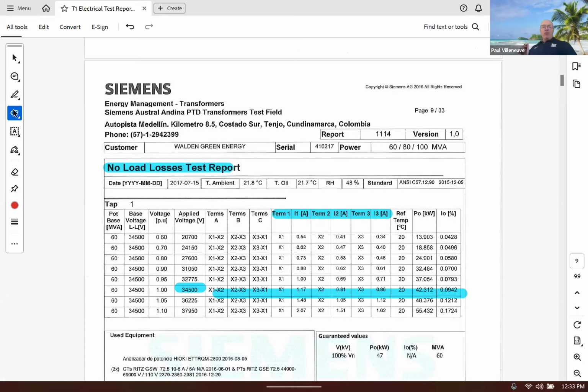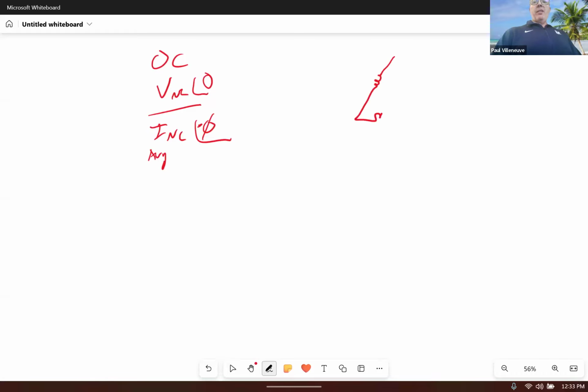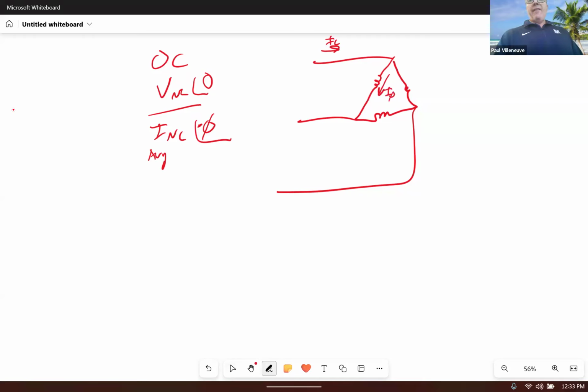That's all I did. But here's where I got to be careful, because on a delta, here's my transformer and my delta windings. I'm measuring this current, which is a line current. The actual impedance I'm trying to get is in that leg. So that's a phase current. So I have to take the no load average and divide that by the square root of 3, right? I've got to convert that to a phase current. Now, the voltage over here is a line voltage, but that's also the exact same voltage across that individual element. So in this case, I don't need to divide the no load voltage by the square root of 3. I've got the answer, right? So it's just V no load at an angle of 0 divided by the average of those currents. That becomes I no load, but a line current. And then I've got to divide that by the square root of 3.